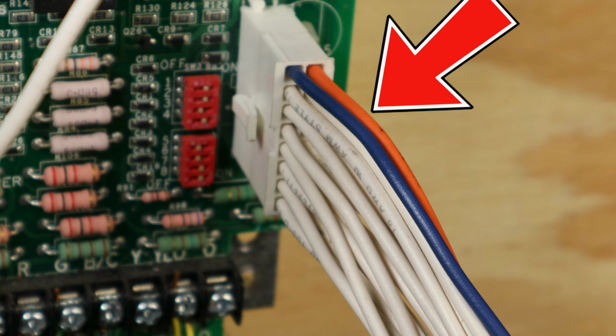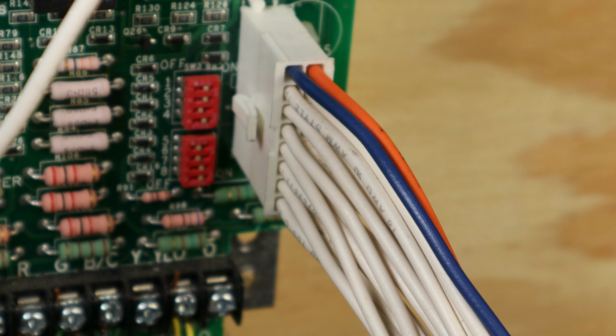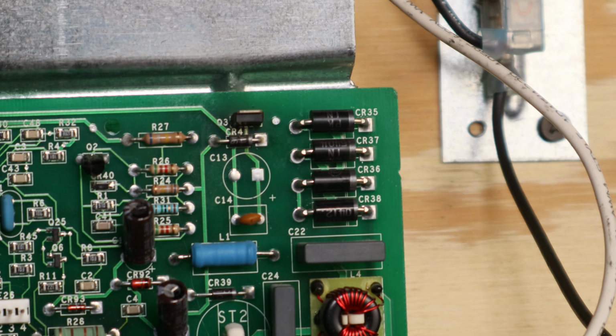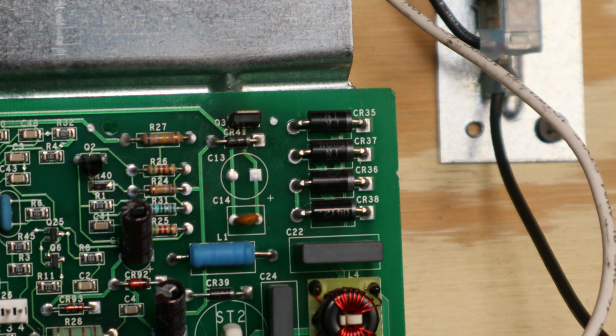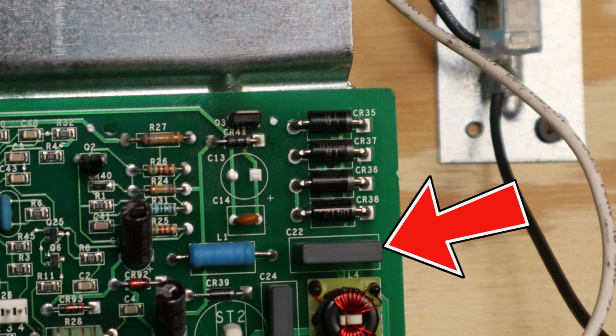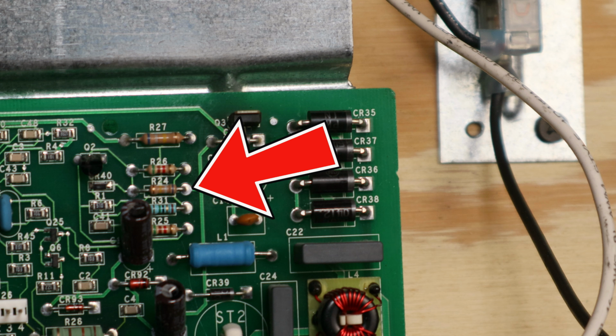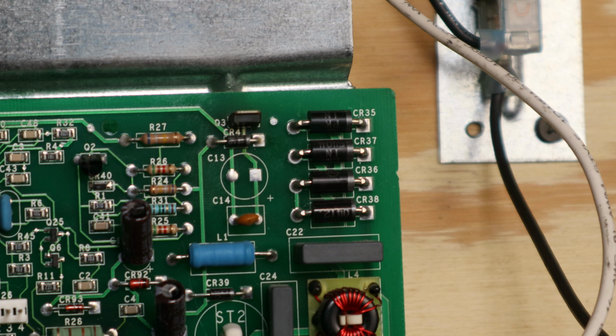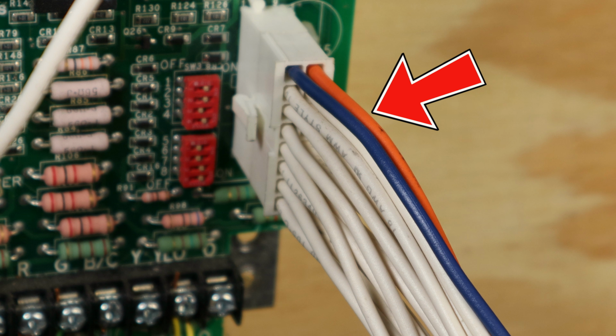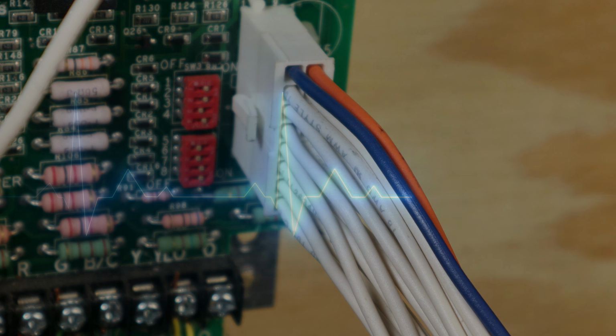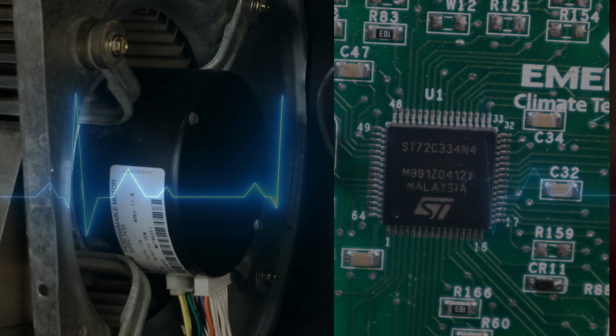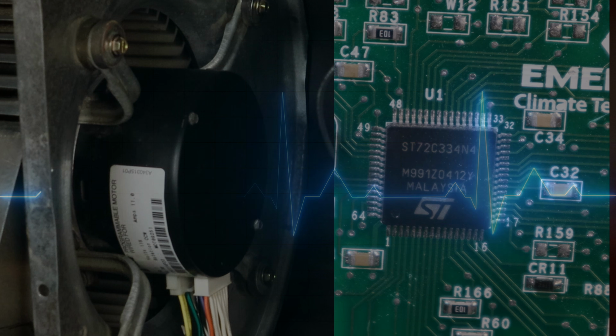Now, the orange and blue wires you see here are something separate. This isn't coming from the microprocessor. This is actually coming from all the way back in the beginning where we started with the diode bridge. Our 24 volt signal off the transformer splits off before it hits that diode bridge and goes through its own cleanup process. It goes through another cap and another diode bridge of its own, and this sends a 5 volt DC electronic signal that acts like the heartbeat of the system. It's a timing sequence signal. So you've got all your logic and sequence going on at the microprocessor, and logic and sequences going on in the control module on the motor, and this timing mechanism keeps them both locked in step.